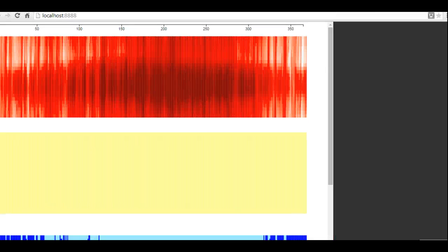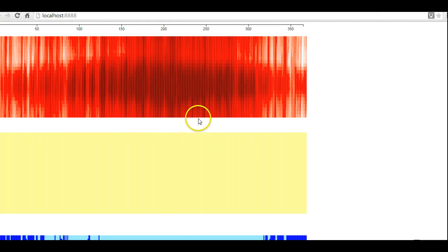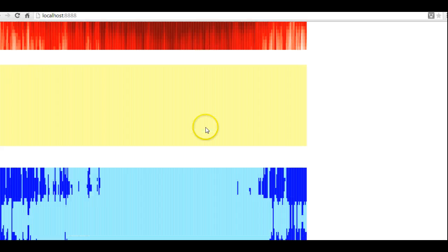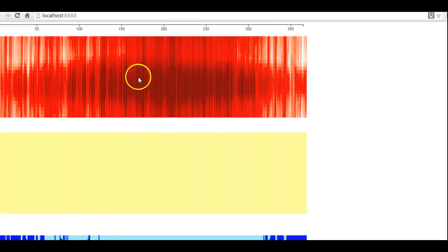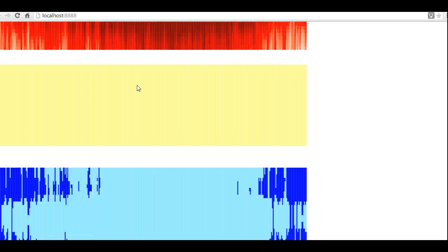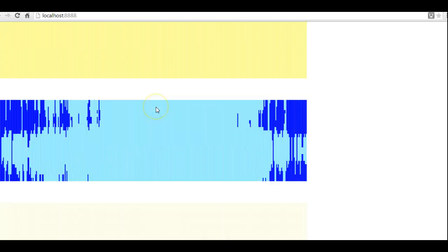Okay, so I made this little visualization using a JavaScript framework called D3, and you'll see basically a few different visualizations here. This first one's the outdoor dry bulb. So we're using a fixed dry bulb economizer, so this should give us some indication. And the second one is the outdoor air flow rate, and you'll see that it's just one value all the time. So it's definitely not what we want.